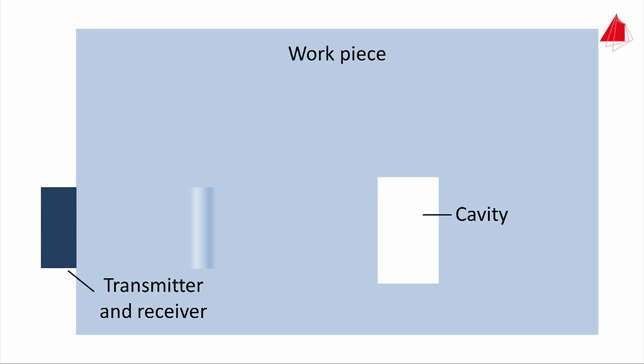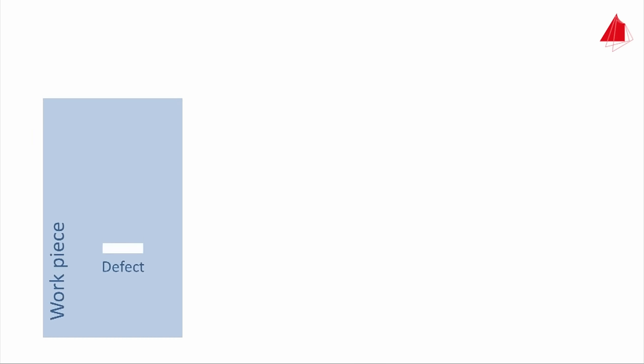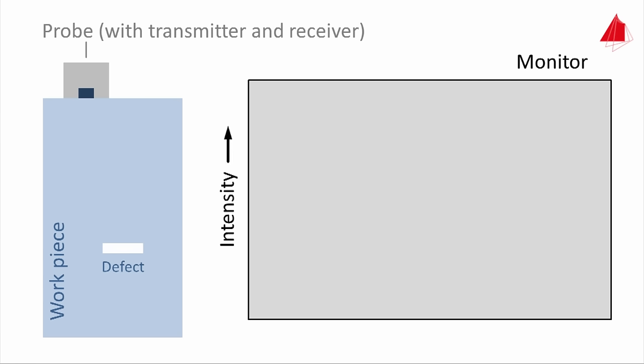For material testing, either the echo of a defect can be utilized—this is the pulse-echo mode—or the phenomenon that hardly any sound waves pass through the imperfection—this is called the through-transmission mode. In pulse-echo mode, a transducer installed in a probe performs both the sending and receiving of the ultrasonic pulse. On a computer monitor, the intensity is plotted upwards on the y-axis and the time towards the right on the x-axis.